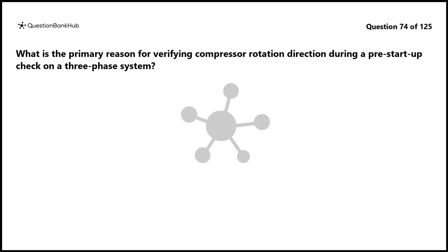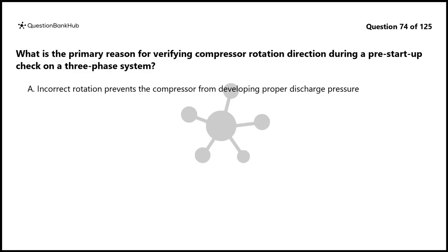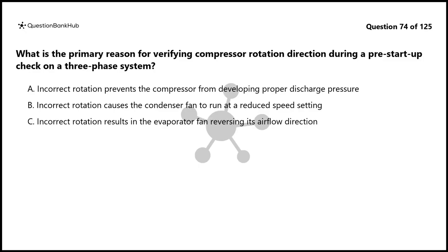Question 74. What is the primary reason for verifying compressor rotation direction during a pre-startup check on a three-phase system? A. Incorrect rotation prevents the compressor from developing proper discharge pressure. B. Incorrect rotation causes the condenser fan to run at a reduced speed setting. C. Incorrect rotation results in the evaporator fan reversing its airflow direction. D. Incorrect rotation causes the crankcase heater to overheat and trip the breaker.